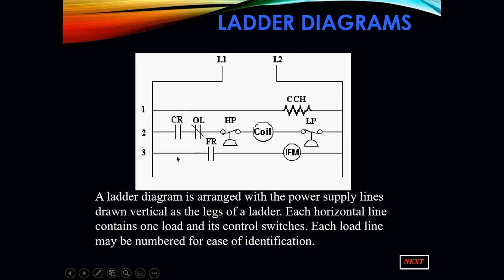Each horizontal part of it could be a rung of the ladder. Here's rung one, here's the next one, two, here's three. Each horizontal line contains at least one load and at least one switch. Each load line may be numbered for ease of identification. You will see this happen on much larger diagrams, especially if you're dealing with commercial sites, where for ease of identification and finding particular components in the diagram, it will give you a legend of what rung or what line number that particular component could be found on.